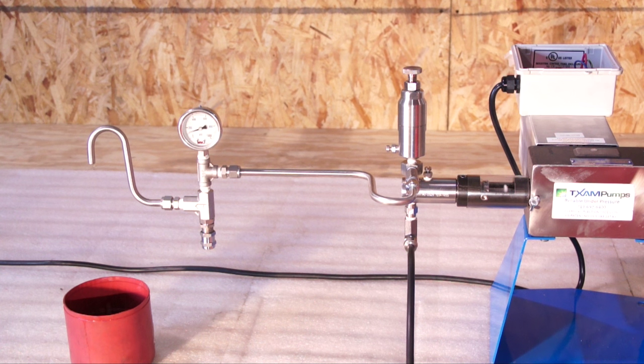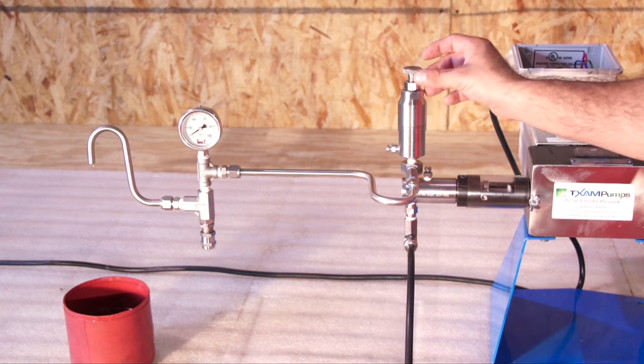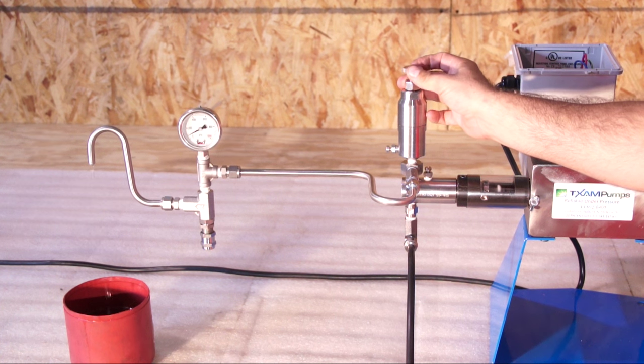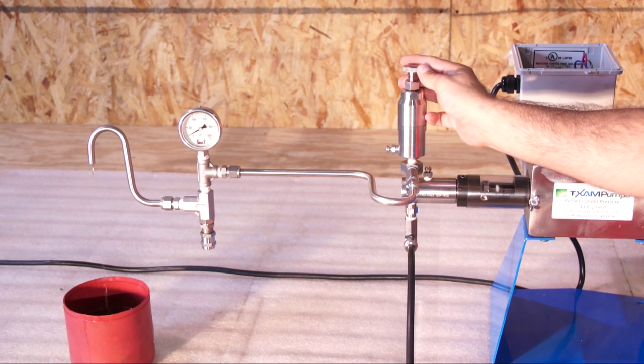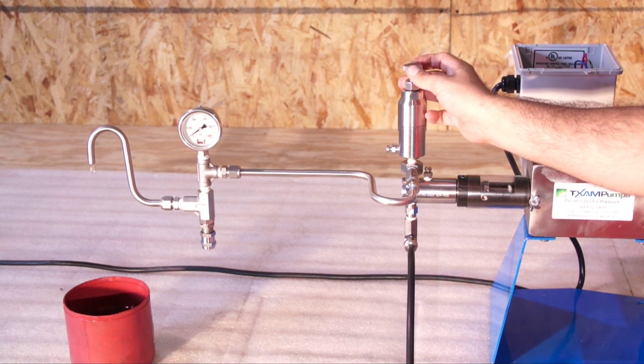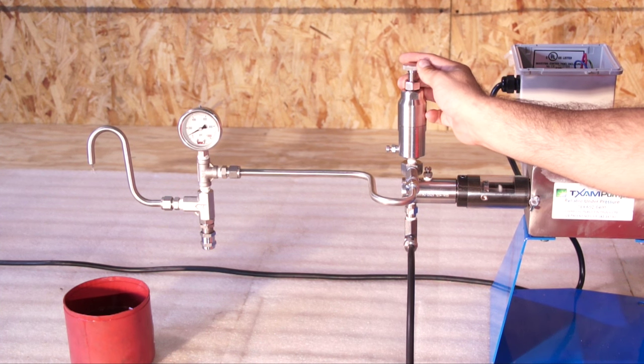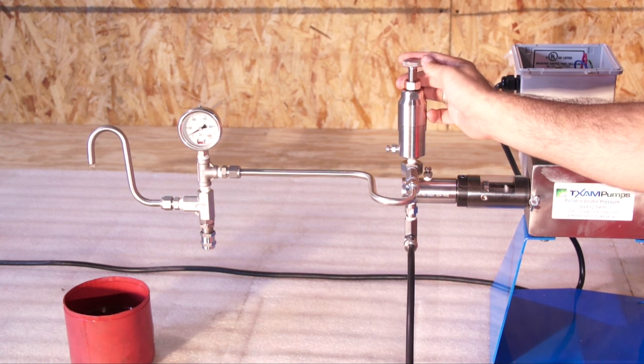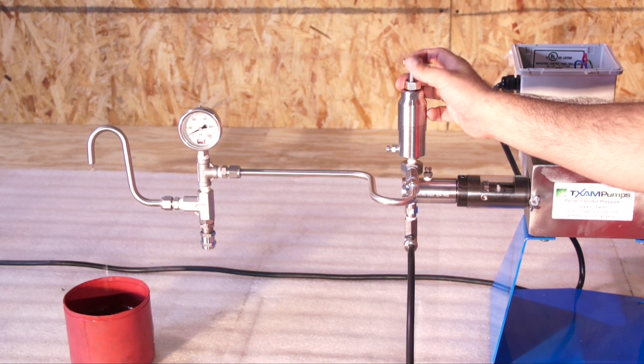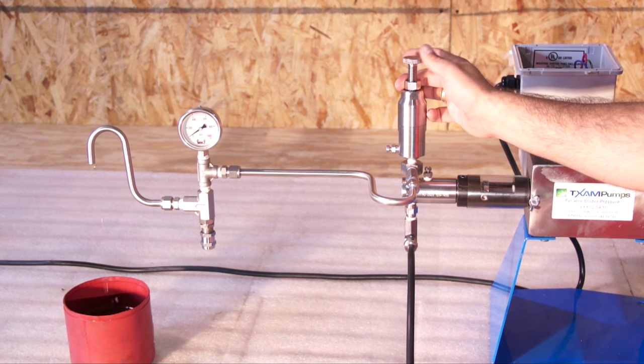After watching the flow control valve installation video, you're now ready to move on to setting your rates. I have set the discharge pressure at 200 psi max. The flow control valve is in the full position, tightened all the way down to the body as far as you can go. As you notice, there's a full stream for the injection. I'm loosening the rate adjustment bolt counterclockwise to reduce my injection rate.